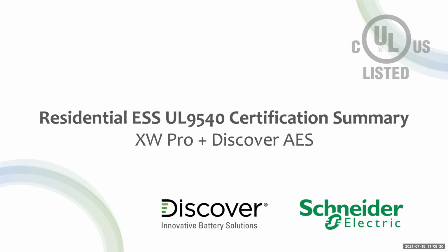I would have to ask for some clarification on the question. Are you speaking of the AC circuits, maybe referring to the distribution panel aspect, or are you talking about DC channels, maybe going to a bus bar solution? Ultimately, from the battery direct, once you're on the DC bus electrically, you can take as many feeds off that as you want. You could take taps off that for any number of devices, as long as your ampacity was sized correctly and the batteries were able to support the current. The number would be infinite.